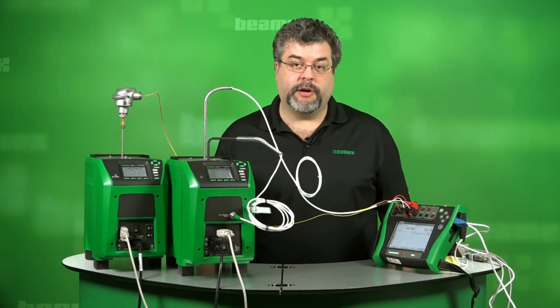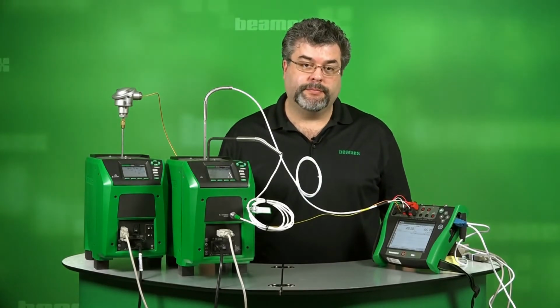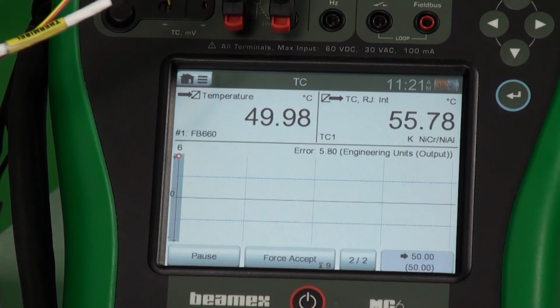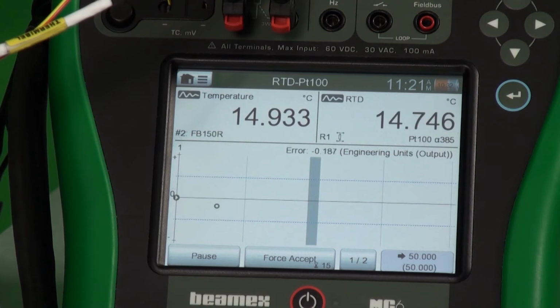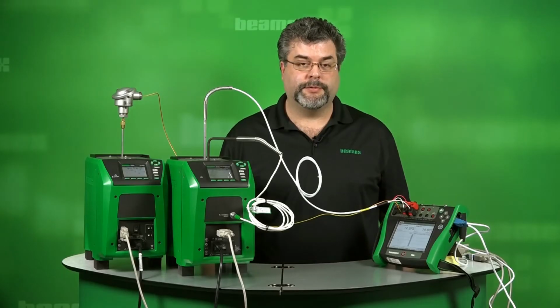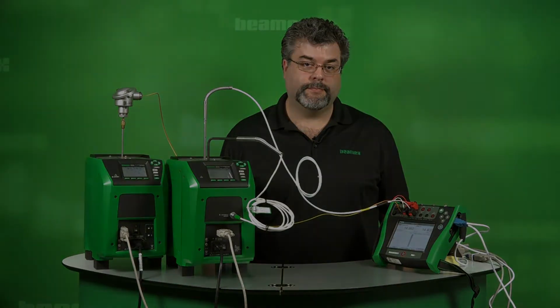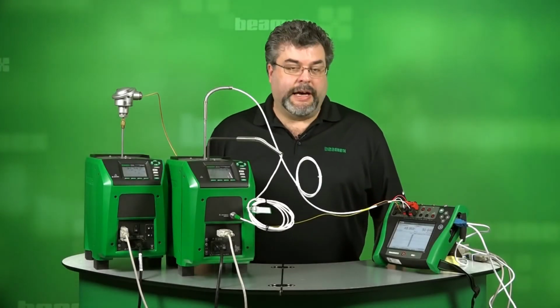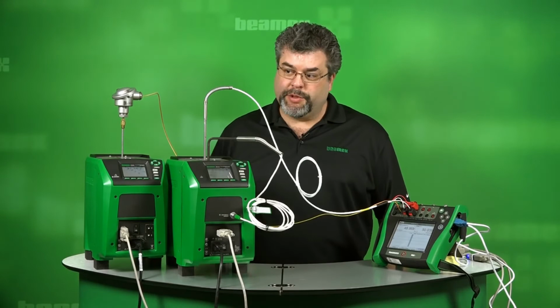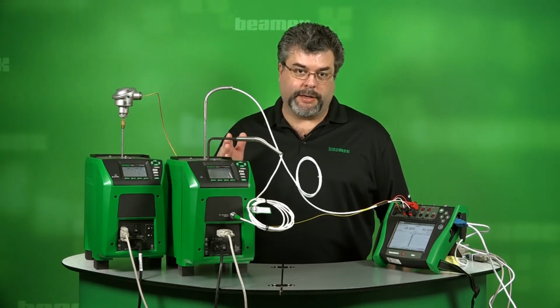We've just reached our first test point on our thermocouple. You see the countdown, our 15-second dwell time. That point is now accepted, so now we go back to our RTD. So we'll hit our second test point. We've now reached our second test point with our RTD. That's on this dry block here.